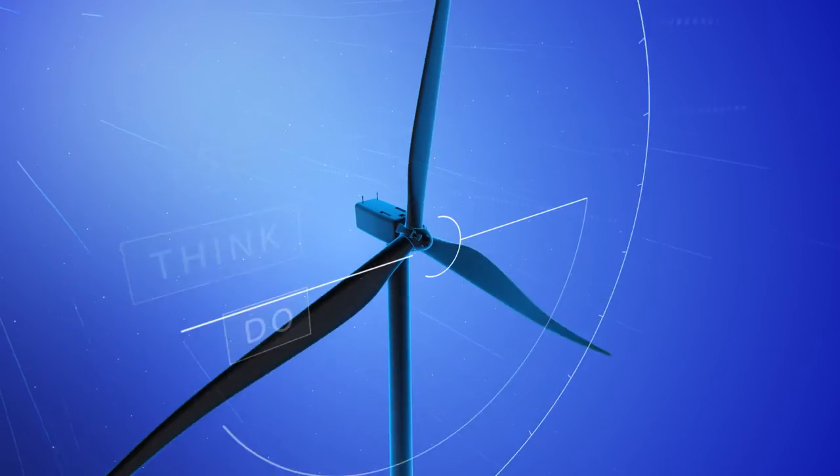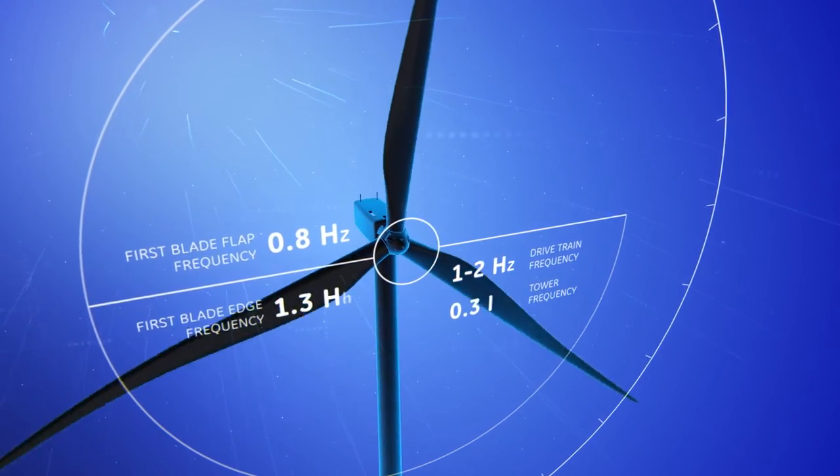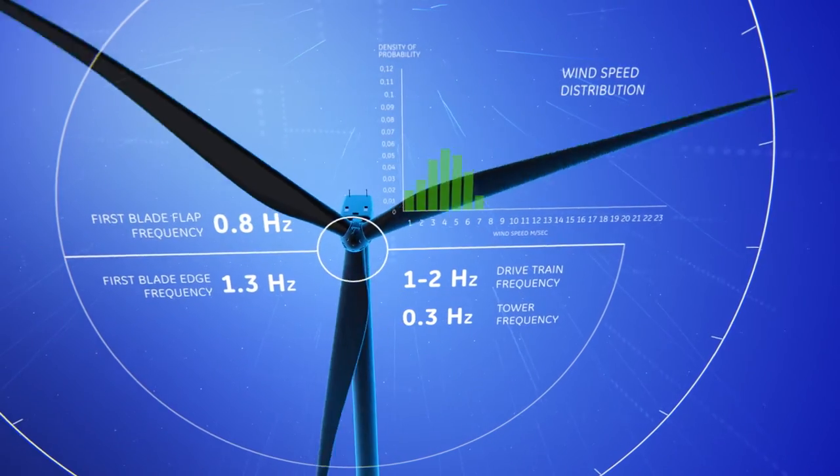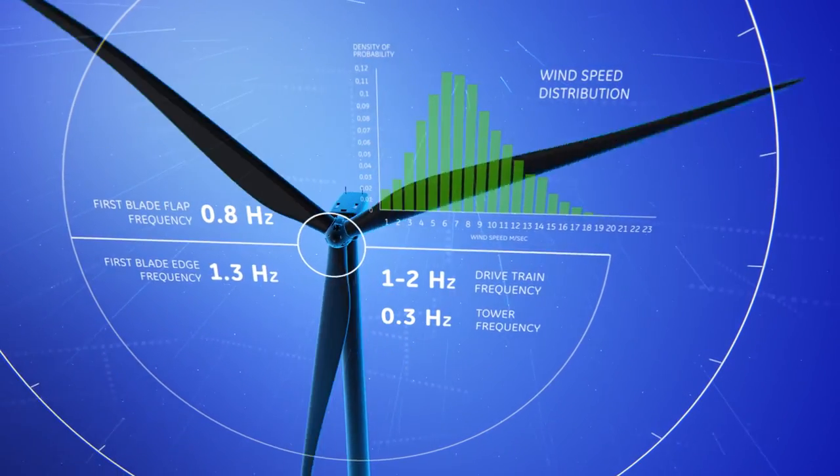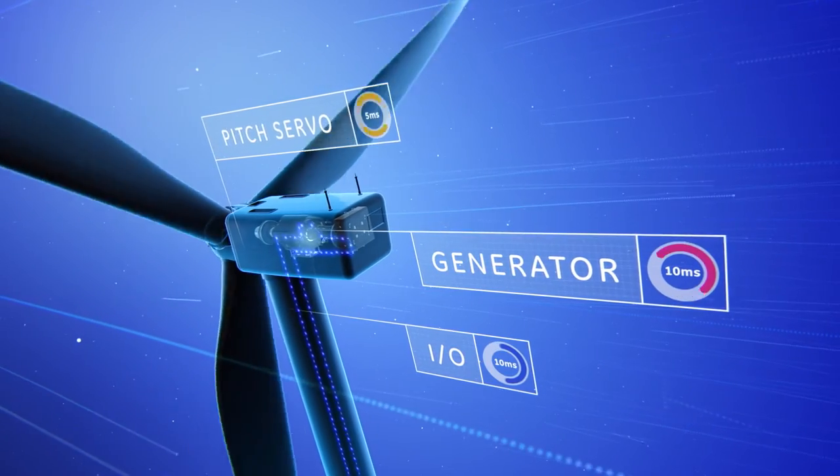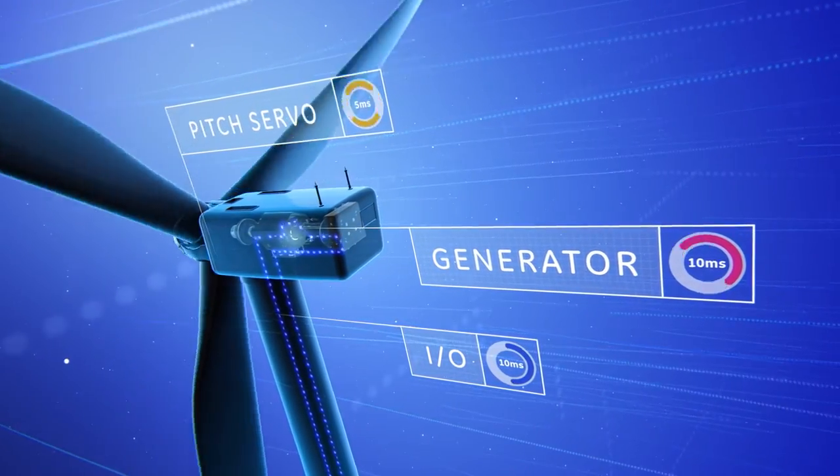The control system must see, think, and do quickly, in real time, at a pace that must be much faster than the physics of the system. Those physics are formidable and include the fast variations of the wind and the natural frequencies of the blade, tower, and other components. To guarantee a reliable and safe system, the controller must see, think, and do 100 times per second.